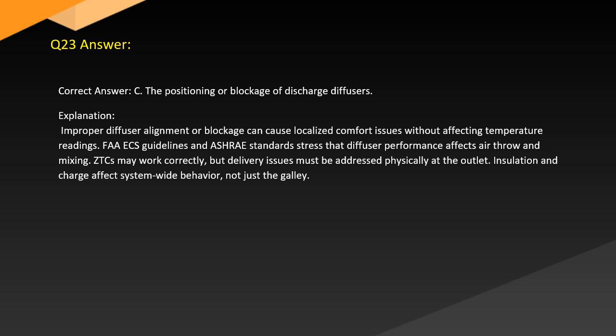Answer. Correct answer C. The positioning or blockage of discharge diffusers. Explanation. Improper diffuser alignment or blockage can cause localized comfort issues without affecting temperature readings. FAA ECS guidelines and ASHRAE standards stress that diffuser performance affects air throw and mixing. The ZTCs may work correctly, but delivery issues must be addressed physically at the outlet. Insulation and charge affect system-wide behavior, not just the galley.